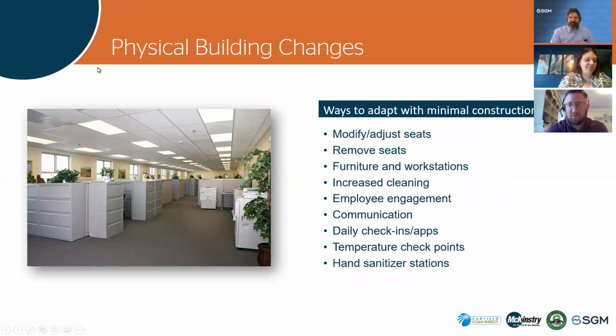Hey, Sarah, real quick, we had a question come through about bathrooms. They wanted to know if we've seen questions or issued guidance around the use of restrooms. From the HVAC standpoint, I'll want to throw in there that you need to ensure that your exhaust fans are running during all occupied times. Restrooms are absolutely a source of these aerosolized droplets. The studies have shown viral RNA in fecal matter, and a lot of times when you use these flush valves, you're aerosolizing droplets. So it is one of the hot spots to consider.